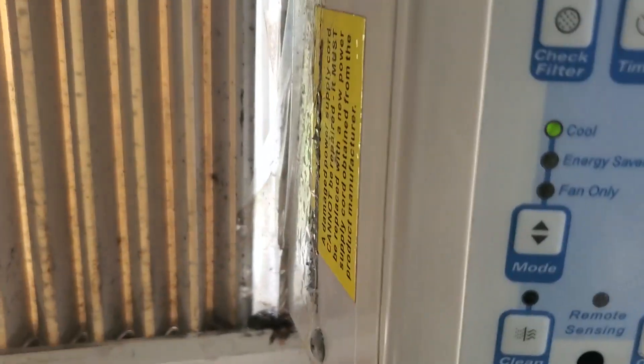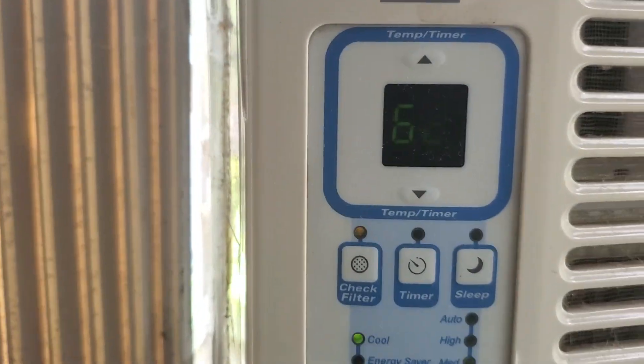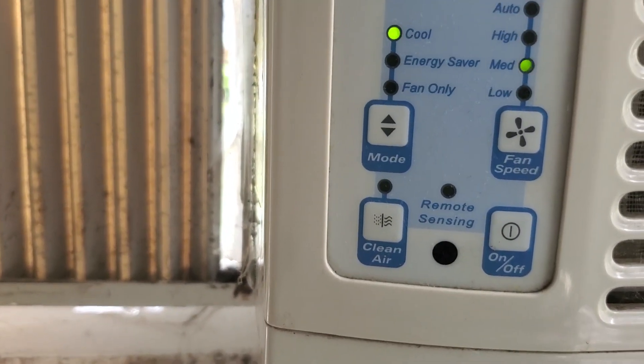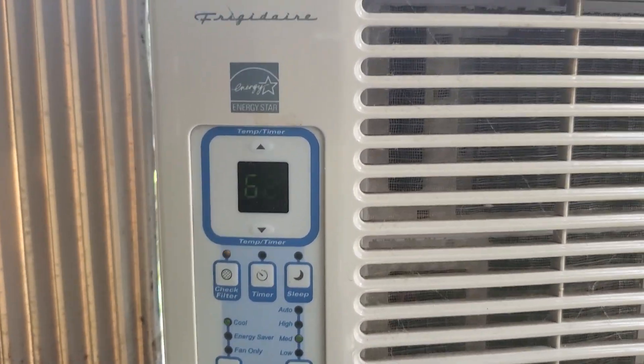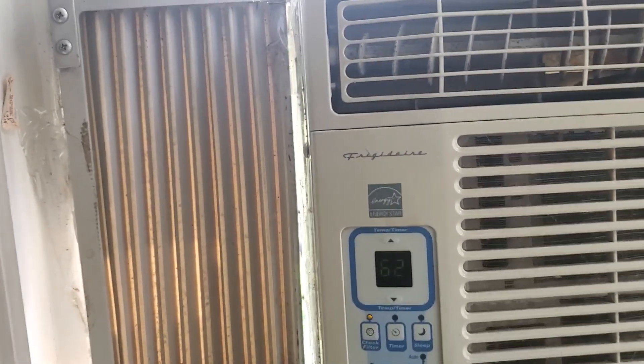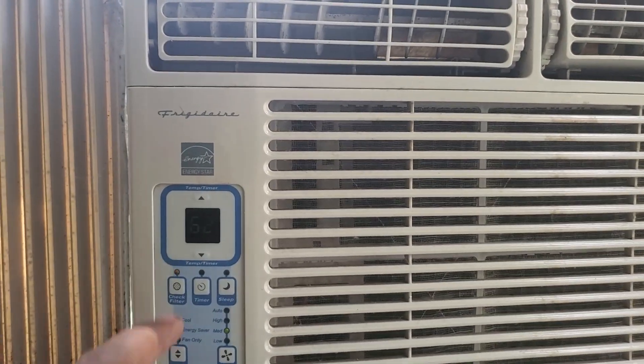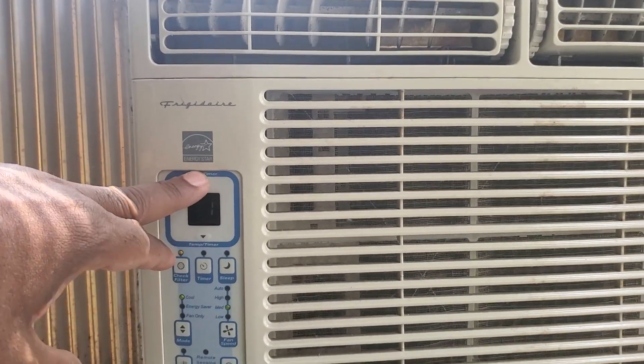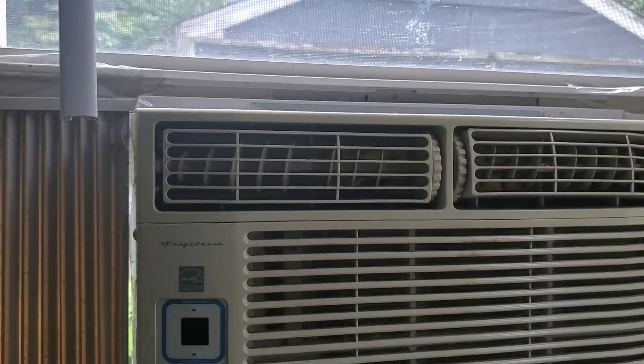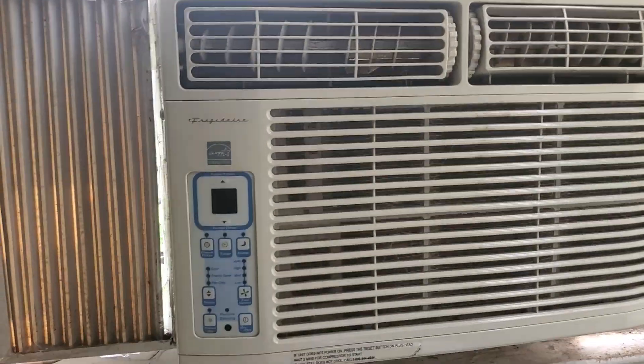I don't feel any cold air from the AC. I don't think it's the fan running — the temperature is at 62 degrees. There we go, you can see what happened — the compressor could not come on. The inverter cannot start this thing when the compressor kicks in — it just dies. Let me bring the thermostat back to 70 and shut this off. Can this thing run the house? The house doesn't use more than this, but with this AC it burns out.